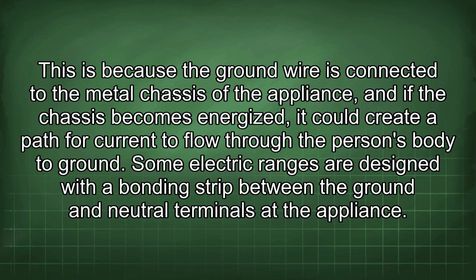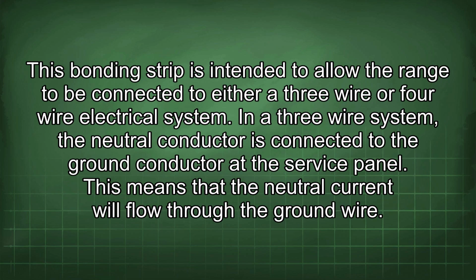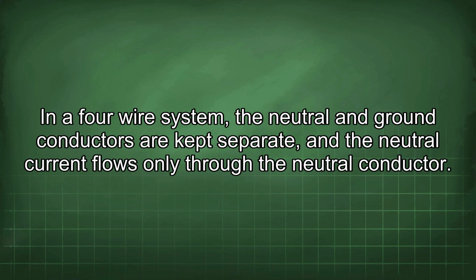Some electric ranges are designed with a bonding strip between the ground and neutral terminals of the appliance. This bonding strip is intended to allow the range to be connected to either a 3-wire or 4-wire electrical system. In a 3-wire system, the neutral conductor is connected to the ground conductor at the service panel. This means that the neutral current will flow through the ground wire. In a 4-wire system, the neutral and ground conductors are kept separate, and the neutral current flows only through the neutral conductor.